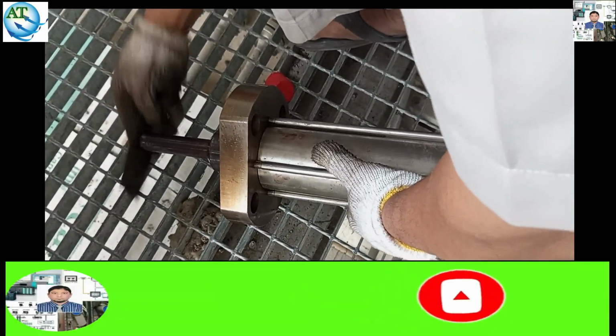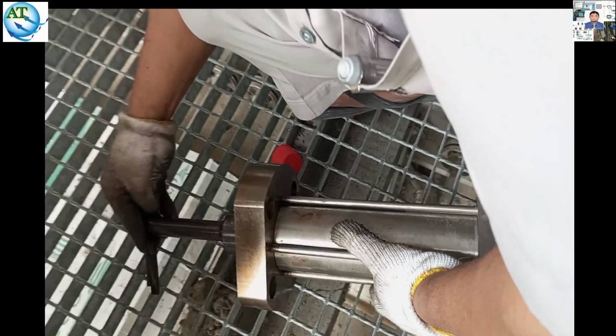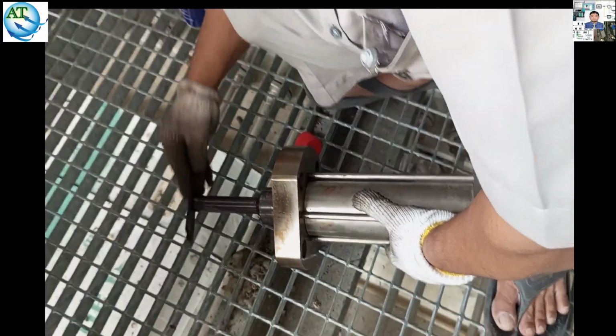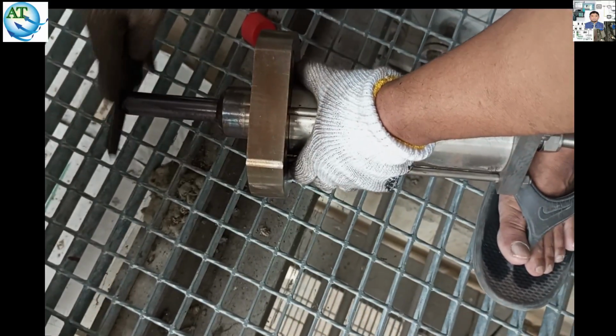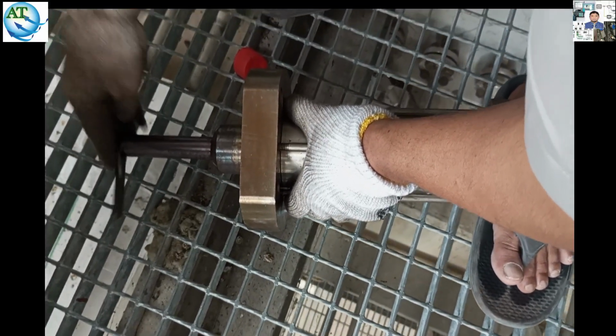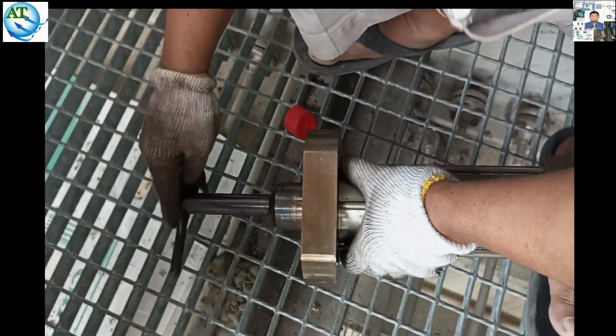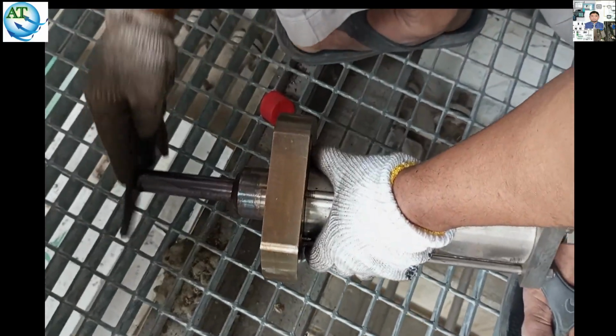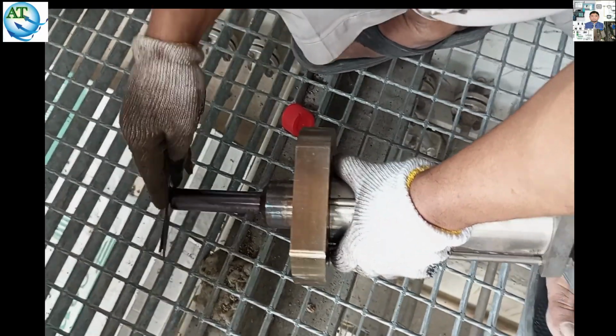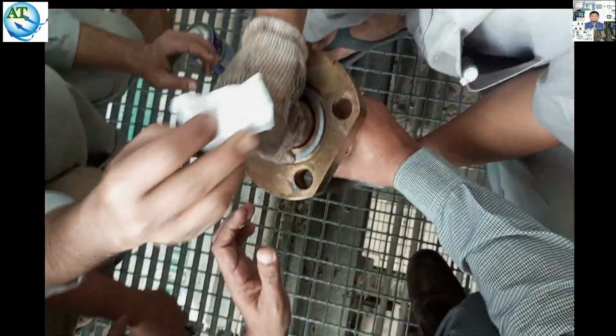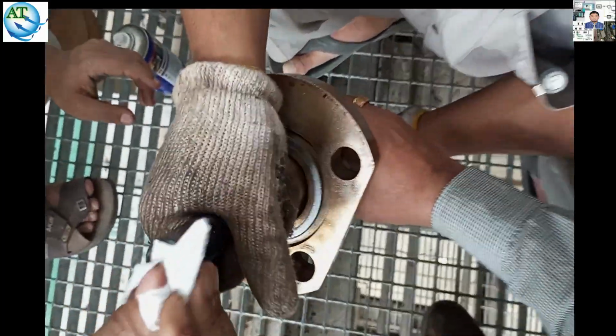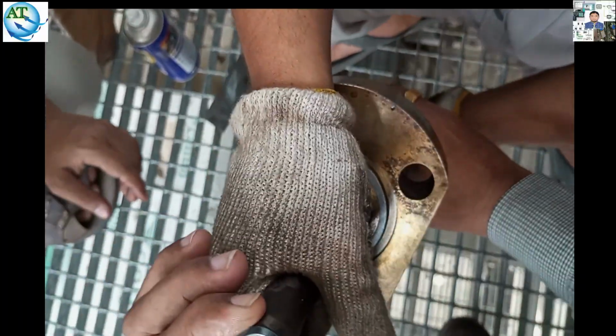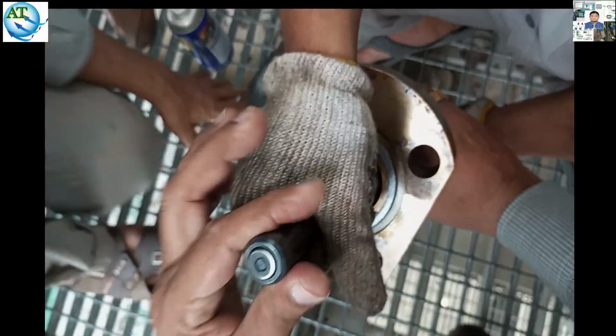After completing this cleaning, we will check whether the igniter is okay or not, because we have tried several times to start the turbine. The gas on-off valves are all opening, and gas is also coming in, showing flow. It is taking some time also, but the ignition cannot come out, and for that the turbine cannot start. For that reason, we have already opened this igniter from the base point. Now we are checking the condition of this igniter.